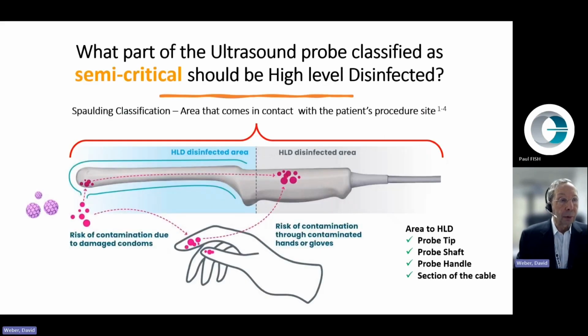Well, let's turn now and look at the probe itself. What part of the ultrasound probe is classified as semi-critical and should be high-level disinfected? Again, under the Spaulding classification, the area that comes in contact with the patient's procedure site, as you can see on the left, should be high-level disinfected. And the risk of contamination due to damaged condoms is always present. So even if the probe has a condom, because condoms may be intrinsically with holes or may fail, we would still do high-level disinfection. We do recommend the use of condoms, but that doesn't mean that you can change the disinfection method.